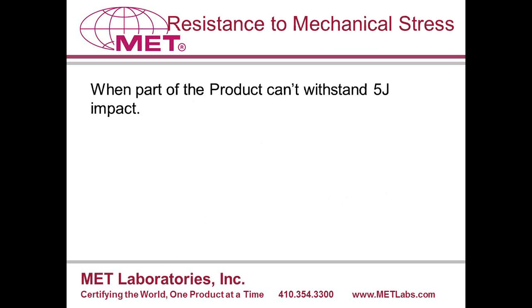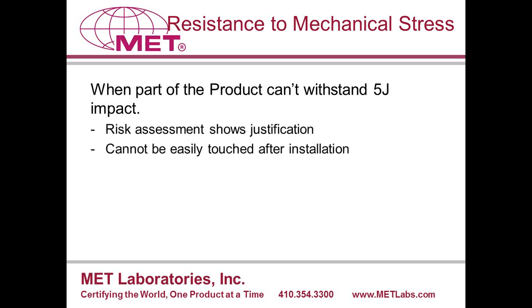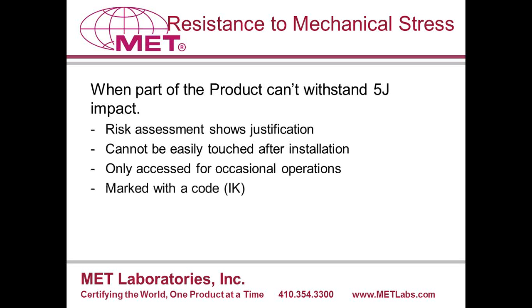When it comes to mechanical stress, there are some cases where a part of the equipment cannot withstand the normal 5-joule impact test. This is now allowable under certain conditions. Specifically, it is justifiable. The part cannot easily be touched. It is only occasionally accessed, and in this case, the part is marked with a special code. Obviously, this is not intended to be used for touchscreens or other parts of the enclosure that are frequently used.